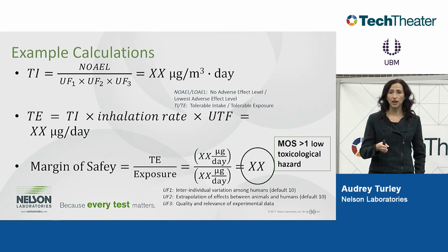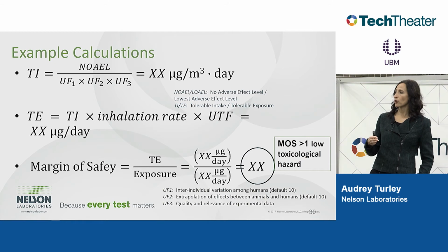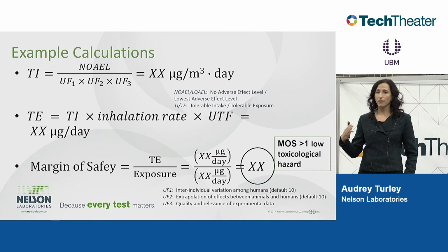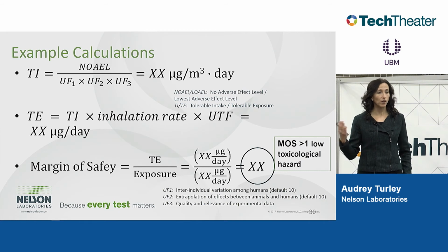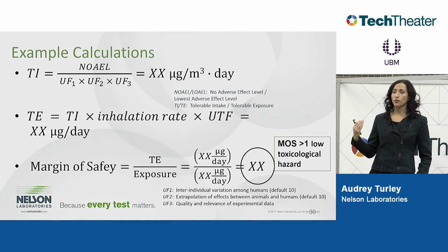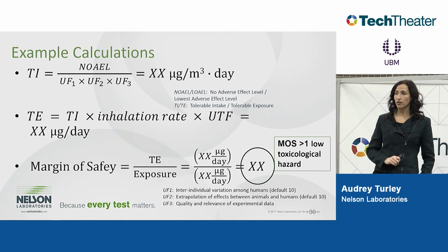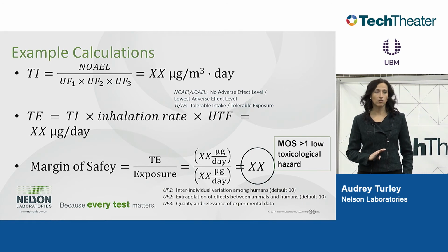Now we're going to bring in the medical device. So we have our tolerable exposure, and then we're going to divide that by the amount that's actually coming off the device and obtain a ratio. So if you have a margin of safety that is greater than 1, that indicates a low toxicological hazard.